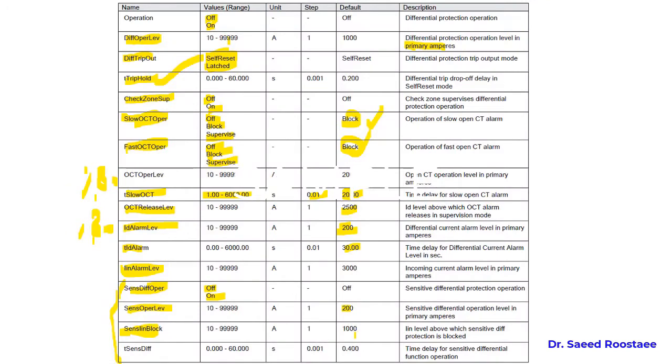The level at which the sensitive differential algorithm is automatically blocked. Here also we should set the value in primary ampere. T sensitive diff is the time delay for the sensitive differential function operation.